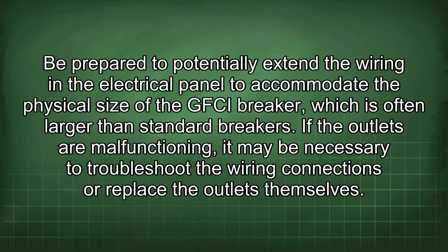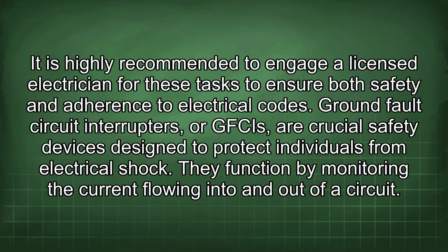Be prepared to potentially extend the wiring in the electrical panel to accommodate the physical size of the GFCI breaker, which is often larger than standard breakers. If the outlets are malfunctioning, it may be necessary to troubleshoot the wiring connections or replace the outlets themselves. It is highly recommended to engage a licensed electrician for these tasks to ensure both safety and adherence to electrical codes.